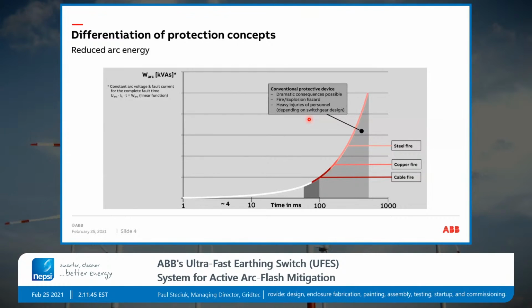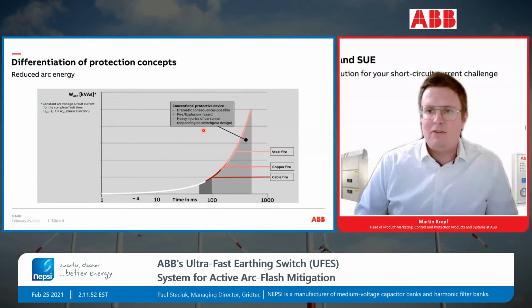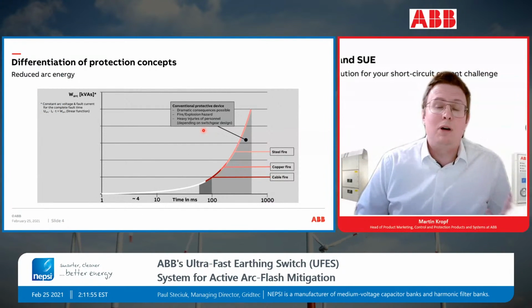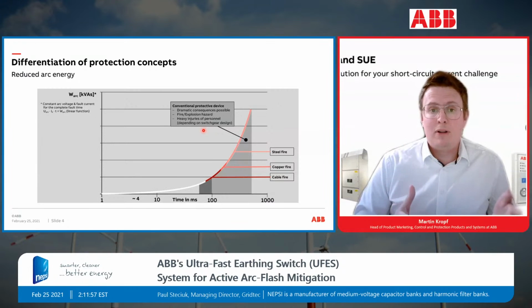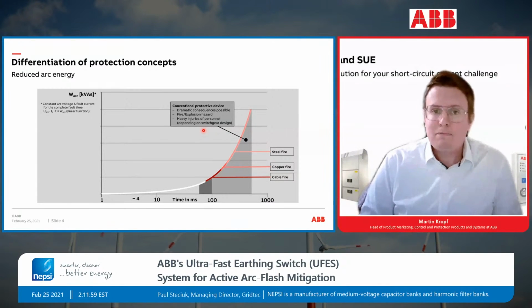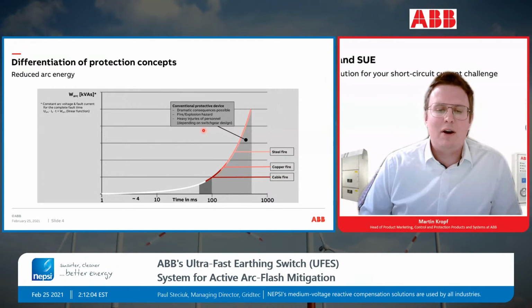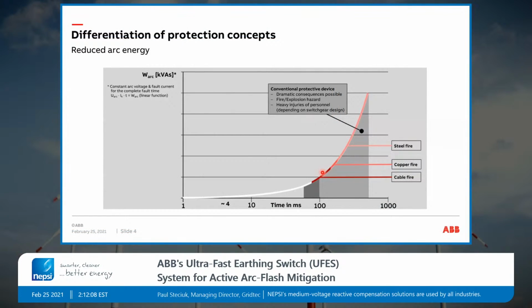If you are fast with this combination, you are above 100 milliseconds. If you have an upstream breaker which you trip, you are maybe also more than 200, 300 milliseconds, and then you interrupt the current. But as you see here in the slide, we actually are in a range of cable fire, copper fire, steel fire maybe. So the damage is really heavy. If somebody is involved directly, we have heavy injuries of the personnel, and we have really dramatic consequences.